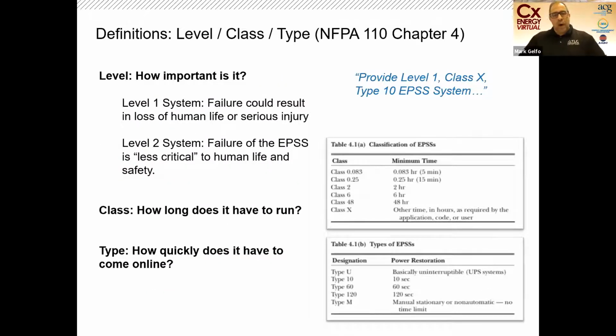There are also different requirements for the level of emergency power system. We talk about Level 1 and Level 2 systems as defined by NFPA 110. Level 1 systems are the most important and critical—most hospitals and critical facilities are going to have Level 1 systems.